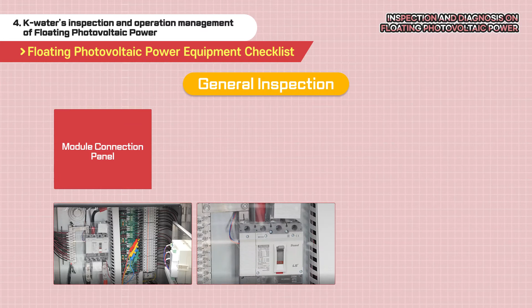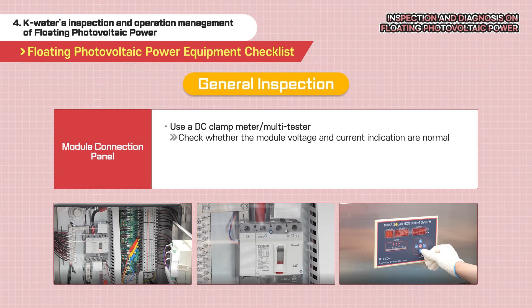The module connection panel collects electricity produced by photovoltaic power generation modules connected in series and parallel and sends it to land transmission connection facilities. Using a DC clamp meter and multi-tester, it measures DC current and voltage and checks the module when each channel indicates different current. In addition, we are checking with an infrared thermal imaging camera to find possible deterioration of the internal electrical equipment to be connected.